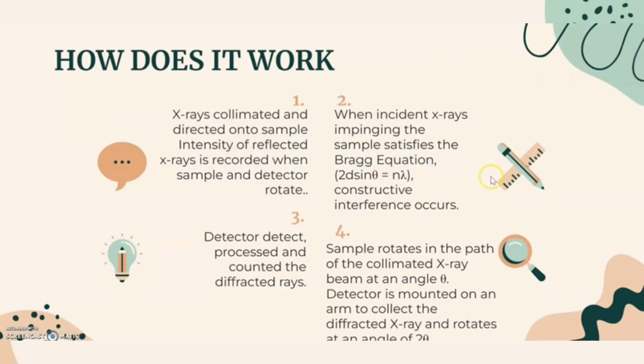So how does XRD work? First of all, the X-rays are collimated and directed onto the sample. The intensity of reflected X-rays is recorded when the sample and detector rotate. When incident X-rays impinging on the sample satisfy the Bragg equation, constructive interference will occur. The detector will detect, process, and count the diffracted X-rays.